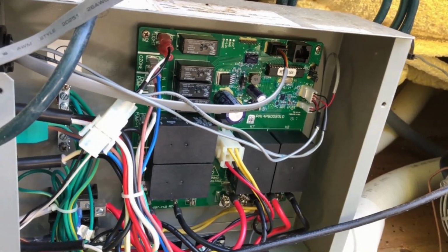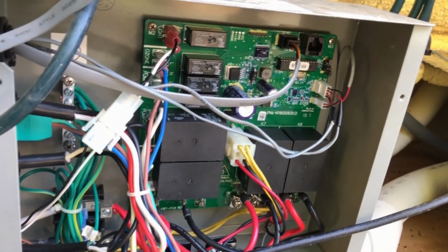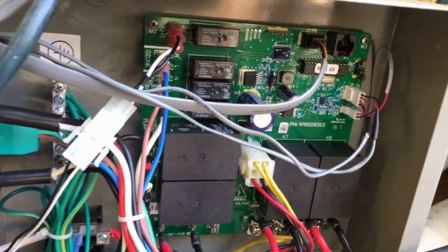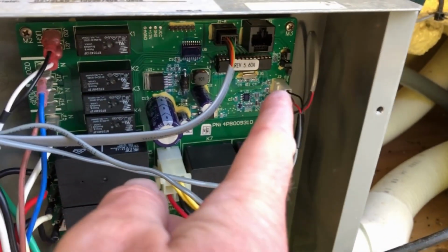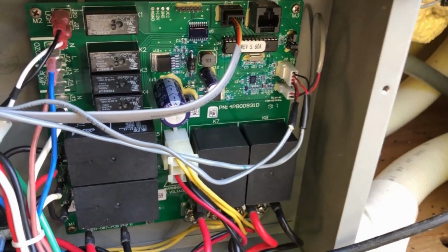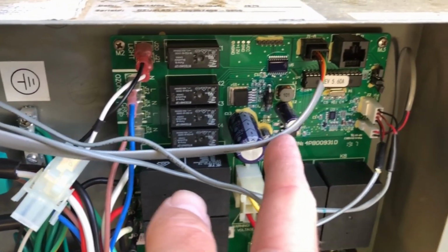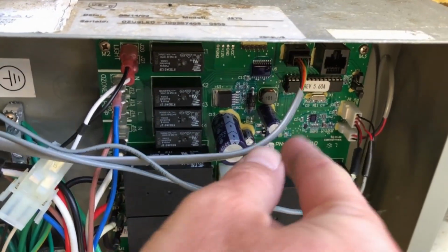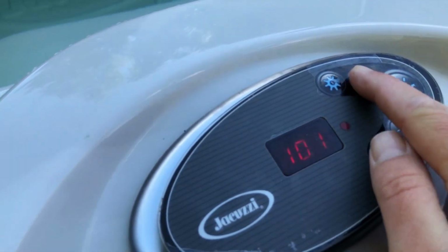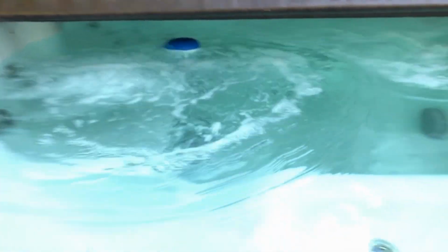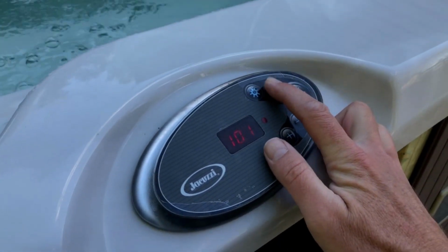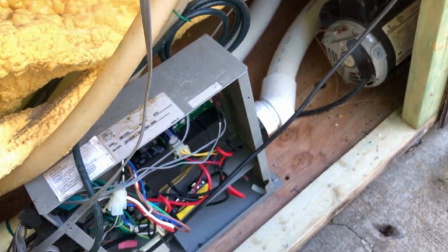All right, we did resolve the problem. Not sure what it was exactly, but I did reseat all the connectors here, particularly the jumper that's 1 pump, 2 pump. I pulled it off and put it back on, and this connector comes from the control panel where the buttons are, the 2 pump button. Maybe that wasn't seated all the way. I pulled it off and reconnected it, then turned my power back on, and I do have my second pump now - all the functions are working. Now I'm just going to turn the power off one more time as I put the metal plate back on and get us all buttoned up.